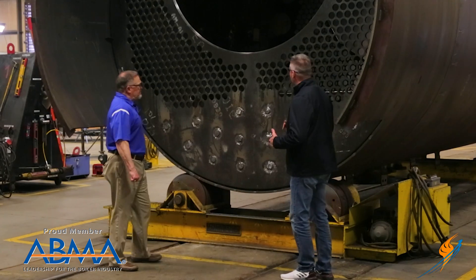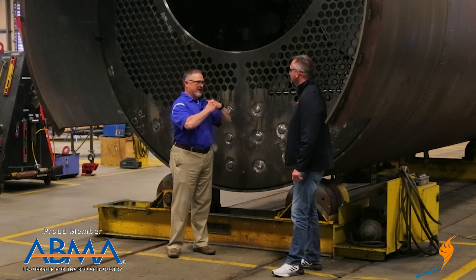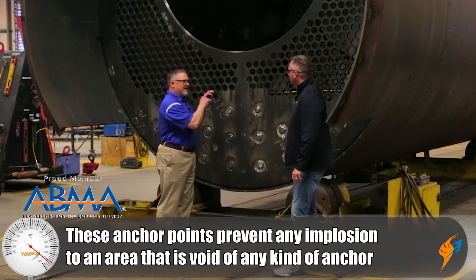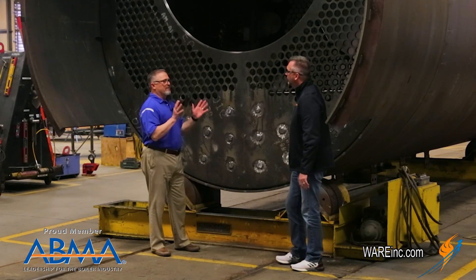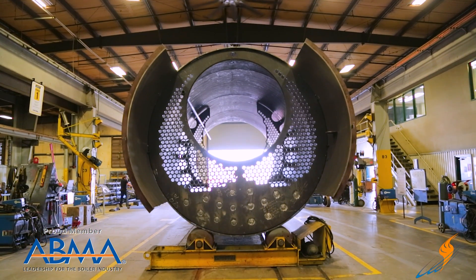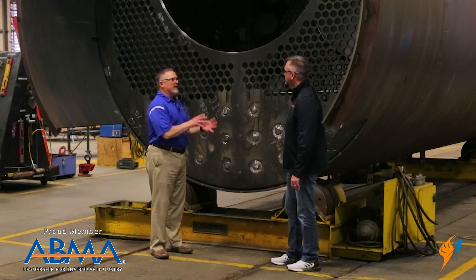As far as putting the stay rods in — what does a stay rod actually do? By ASME code section one, any void area that doesn't already have an anchor such as a tube joint, that bare space needs to have another anchoring point to make sure there's no implosion to that area. You're basically trying to keep that tube sheet from warping. With the buildup of pressure internally, water being on the outside of the tubes, you've got a very large area in a flat section — the stay rod makes sure that flat area without an anchor is secured.